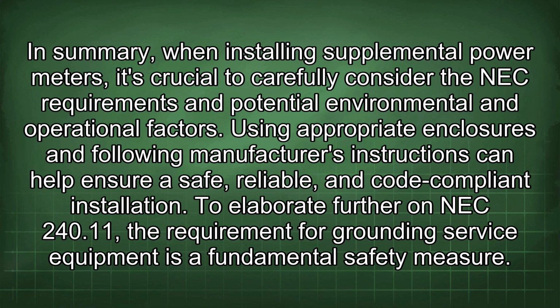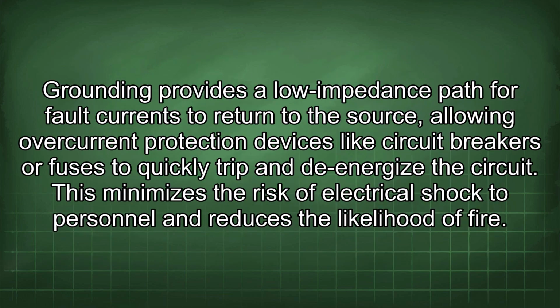To elaborate further on NEC 240.11, the requirement for grounding service equipment is a fundamental safety measure. Grounding provides a low impedance path for fault currents to return to the source, allowing overcurrent protection devices like circuit breakers or fuses to quickly trip and de-energize the circuit. This minimizes the risk of electrical shock to personnel and reduces the likelihood of fire.